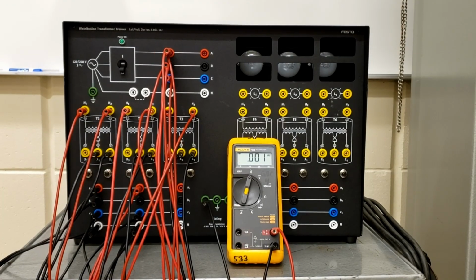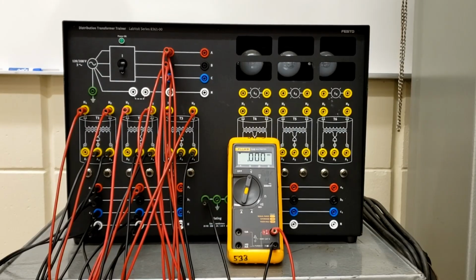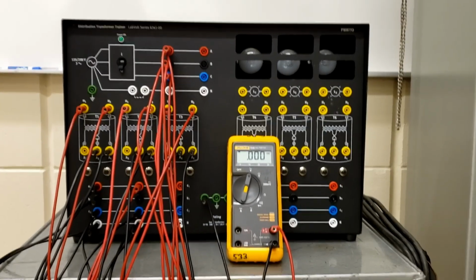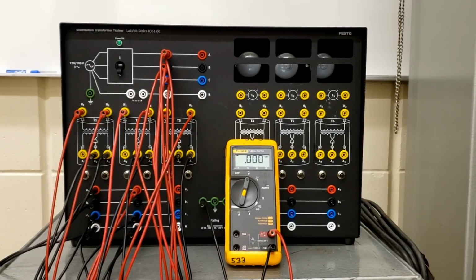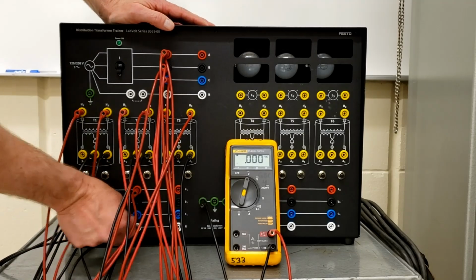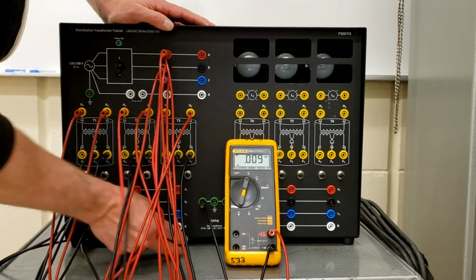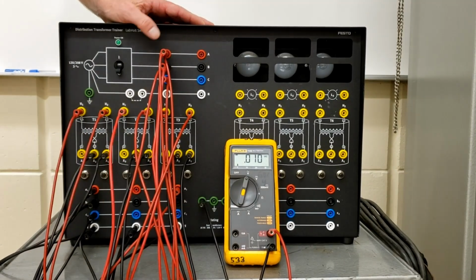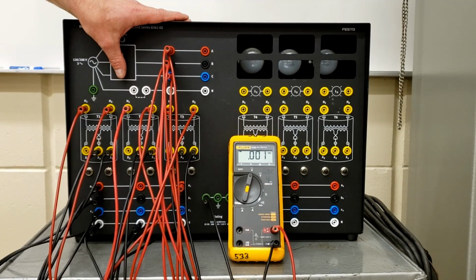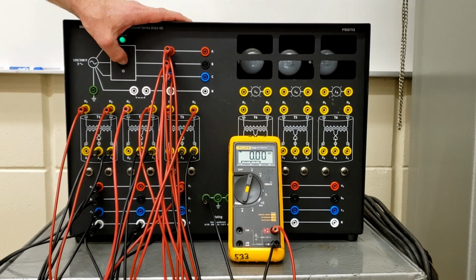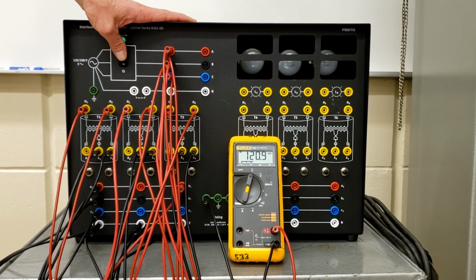If we flip to page 22, it's asking for the voltage between A1 and neutral. Let's move this down to the neutral, and move this over so you can see it. So for A1 and neutral, if we had 208 as the line voltage, we should have 120 as the phase voltage. There we go, line A to neutral is 120.